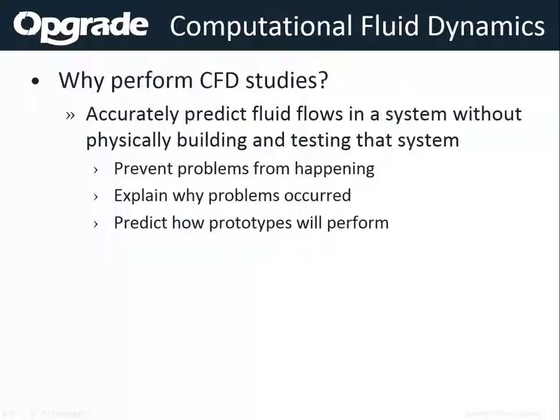We looked at an exchanger, a condenser actually, once. We took a 2D slice of it, and the tubes on the bottom were failing. We thought maybe the steam was impinging somehow. Well, the steam was blasting out of the sparger, coming down around the sides, and this jet of steam was waving back and forth across the bottom tubes exactly where they were failing. That's what was going on. We put some baffles in to slow down the steam and prevent that from happening. Those are some of the ways CFD can be very valuable.